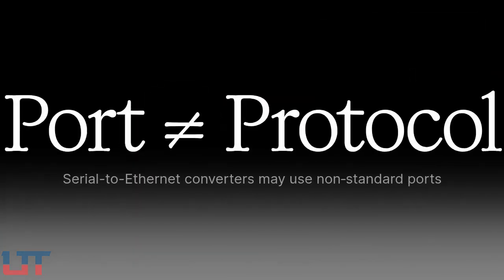From the SCADA server's perspective, it's polling a Modbus TCP device. From the device's perspective, it's doing exactly what it's always done, sending data over serial connection. The security implication. The port number used by a serial to Ethernet converter depends on how it was configured, not on a standard. Some use port 502, some use port 503. Some use an arbitrary high port chosen during commissioning years ago. The actual protocol is still Modbus, but it won't appear on port 502 in your firewall logs. It will appear on whatever port the converter was set to.